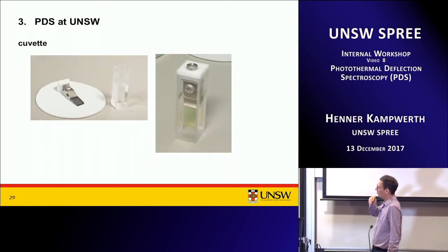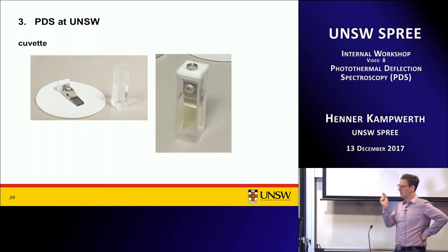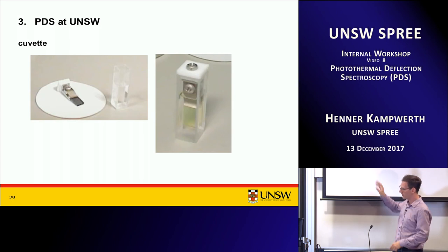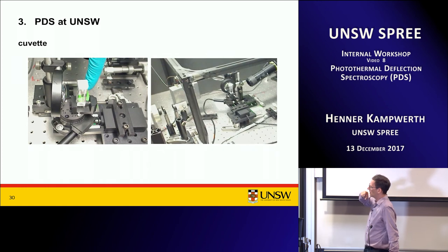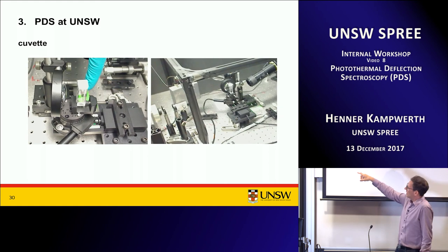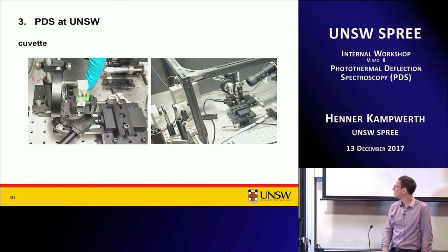This is the cuvette and sample holder — a fairly small thing, about one centimeter by one centimeter at the base. You have a small substrate sample clamped by the lid, put into a cuvette filled with liquid, and placed in a sample holder which is an automated rotation and translation stage. On the right-hand side there's a camera so you can actually see what you're doing and how to align it — it's a fiddly thing.